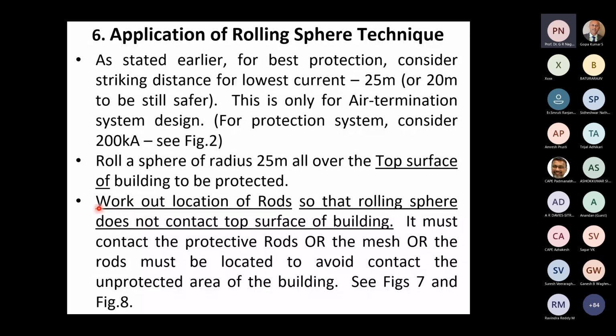So now, once you roll the sphere on the top surface completely, this rolling sphere, when it's rolling all over the top surface, must contact either the protective rods or the mesh, or the rods must be located to avoid contact with the unprotected area of the building. Now, this is the basic principle.